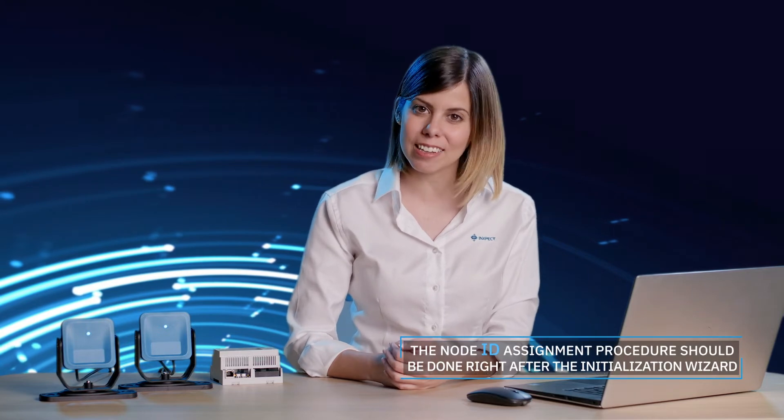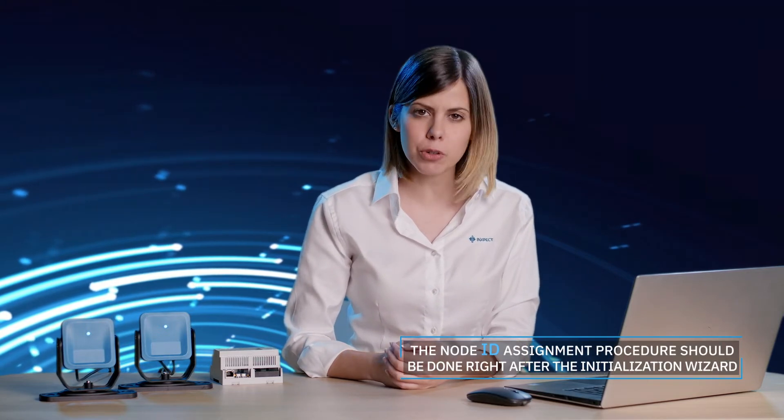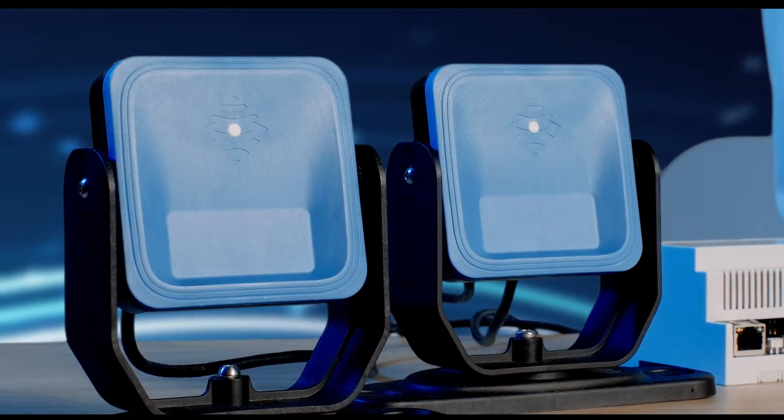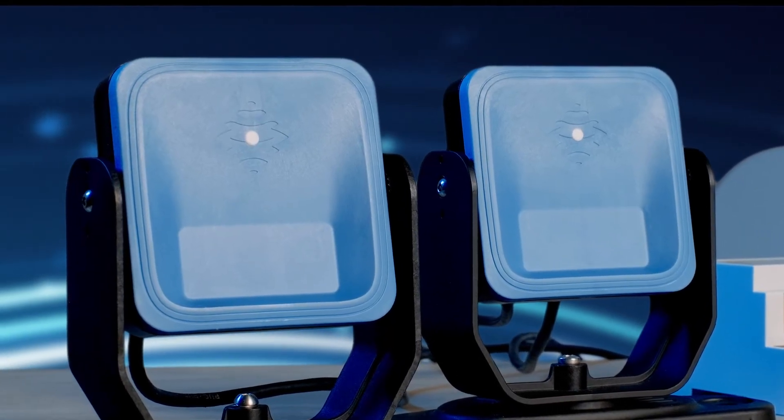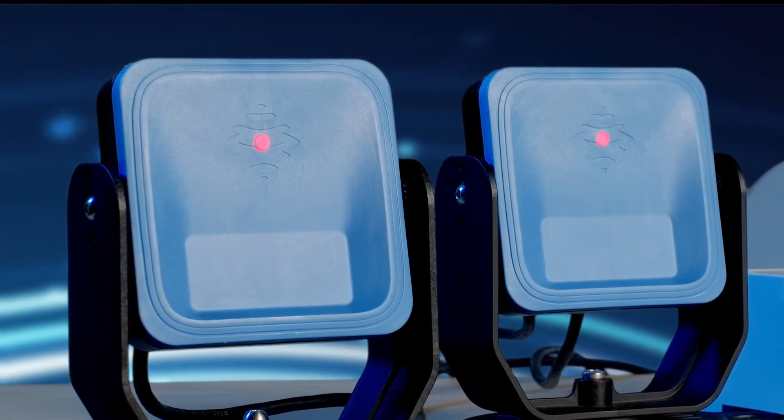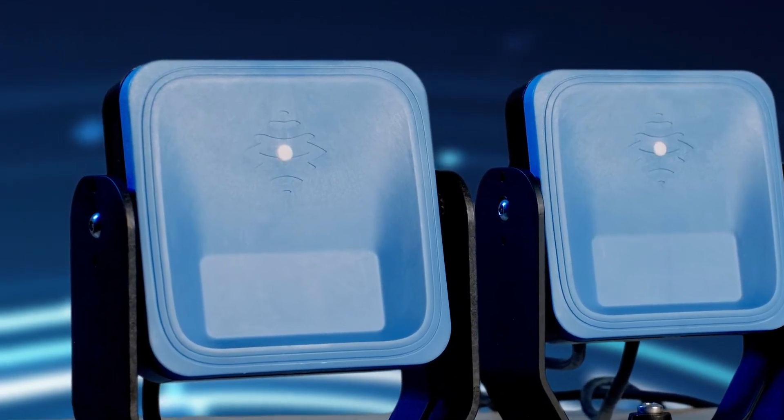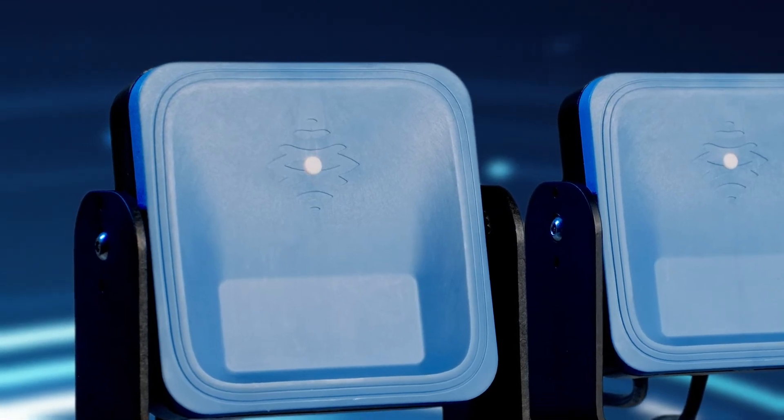The node ID assignment section is where each connected sensor gets its unique identifier, which in turn allows the control unit to recognize and identify the sensors along the chain. You can quickly recognize sensors without an identifier. Their LED will flash twice. There are three ways to assign the node ID to a sensor.